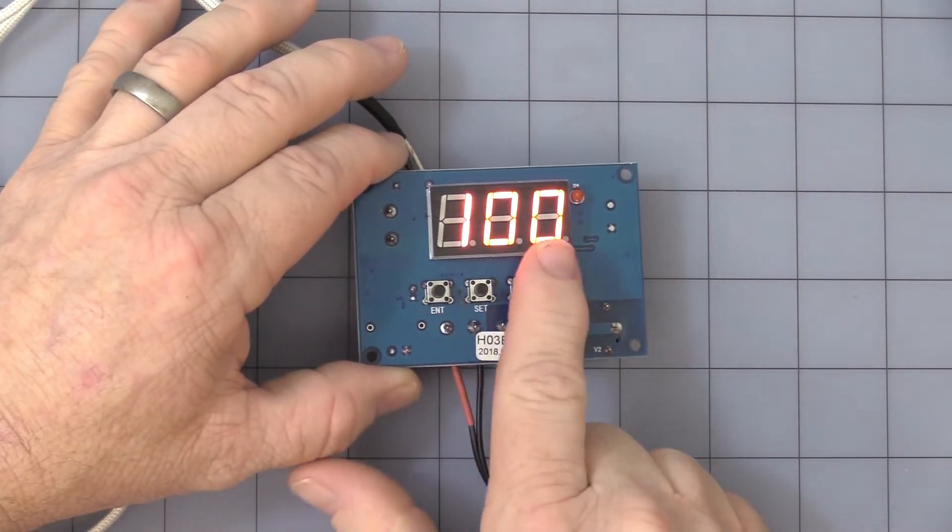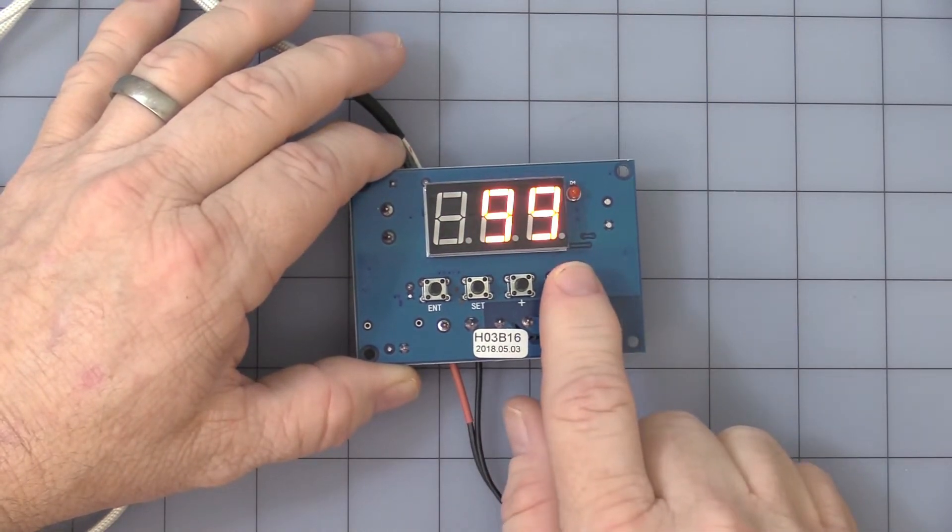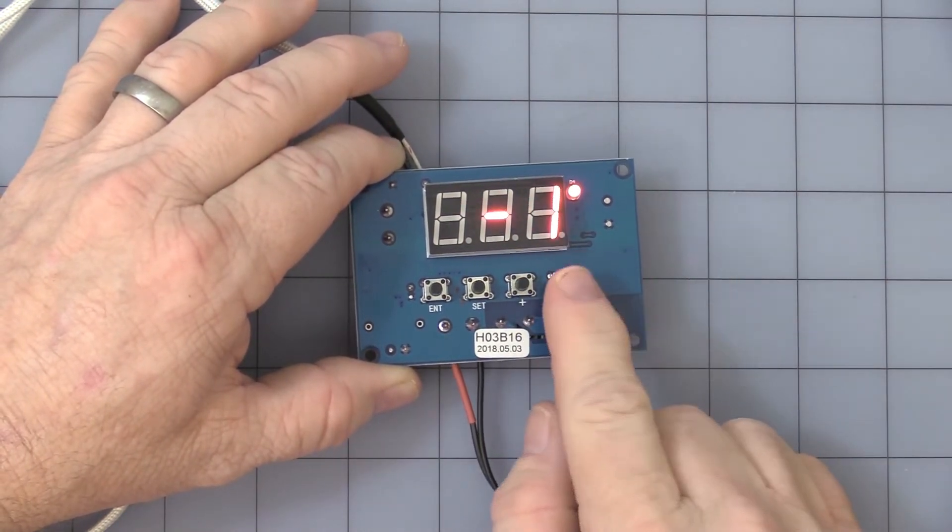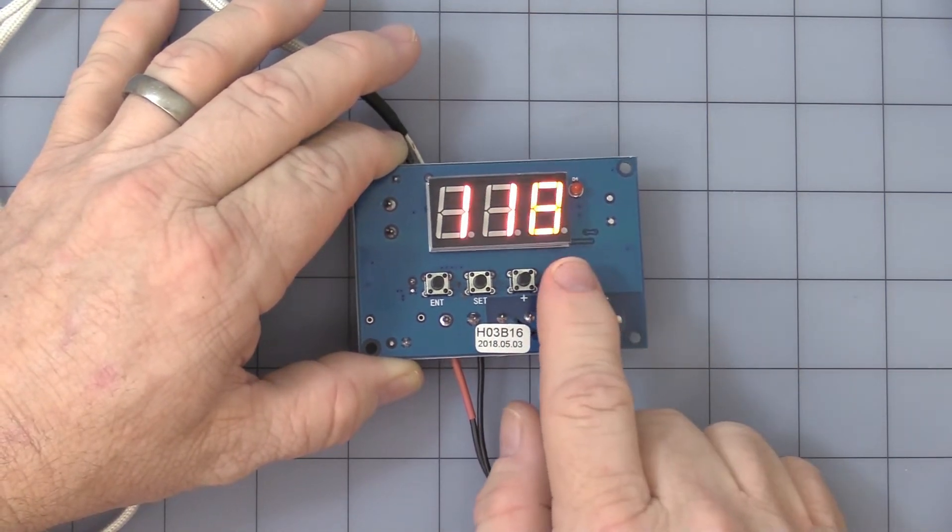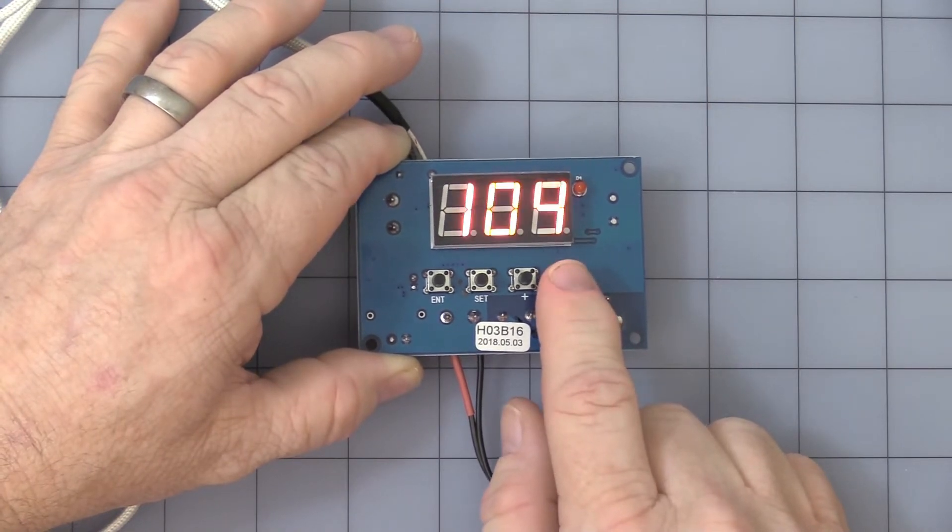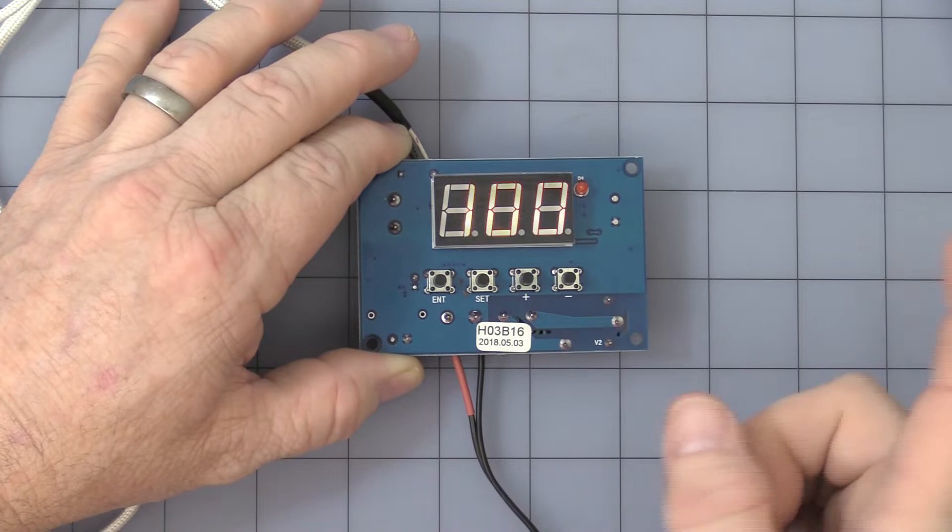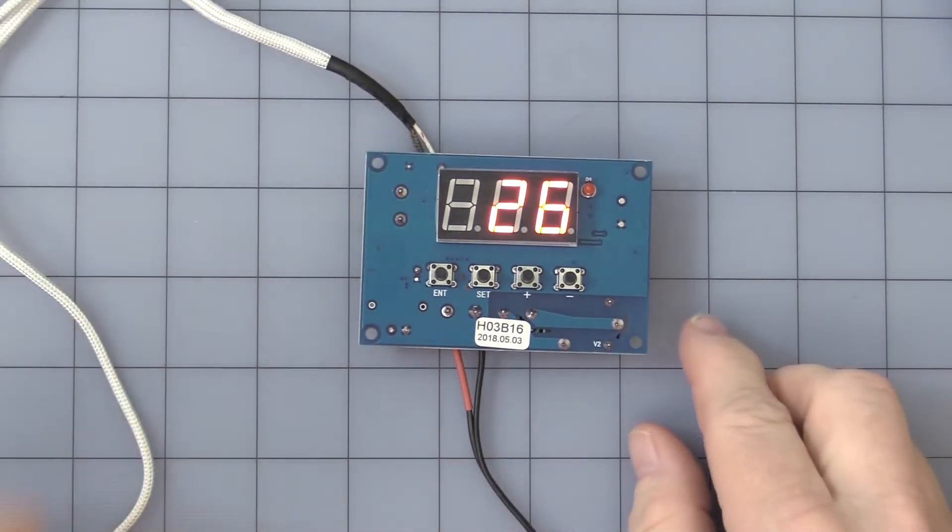And that displays the temperature set point. When it's flashing, you can just simply use the plus and minus button to set whatever temperature you like. 100 degrees C seems to work well for demonstration purposes, so we'll keep it at that. You can hit enter, and it starts displaying ambient air temperature.